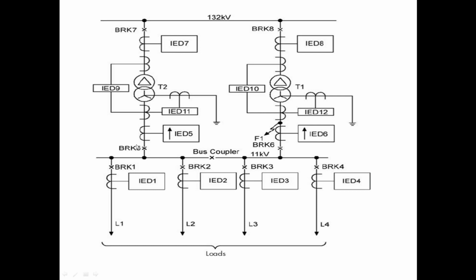But the thing is, even though breaker 5 is tripped, the power supply from the upstream 132 kV substation is still in running condition. So it is feeding the power supply to the primary side of the transformer, but on the secondary side it is tripped. To avoid this issue, we need some more relays to protect our transformers. That's why we are using this intertrip send relay.